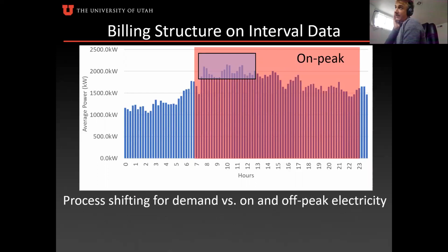So you have a process that's happening from 8 to 12, as Michael kind of observed earlier with that weekly power draw data. Do we want to move it more into on-peak hours or away from on-peak hours? You'd want to move into off-peak hours. Awesome. Yeah. So that's kind of just a solid approach: we want to think about how we can run processes during off-peak hours, if that's possible.